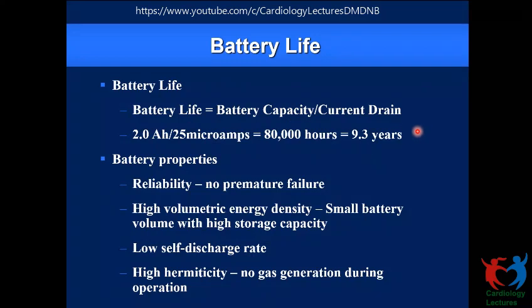But it's difficult for us to calculate. The programmer actually is able to measure what is the continuous current drain based on the history of the pacing and sensing that happens. And it applies that and tells us how much the battery is going to last from the time when we are interrogating. So that's the way it is calculated. So we don't have to calculate that. So it's good to go by the programmer suggestion when we interrogate. And again, it's not absolute. So there is likely to be a little bit of variation, so we need to keep that in mind as well.